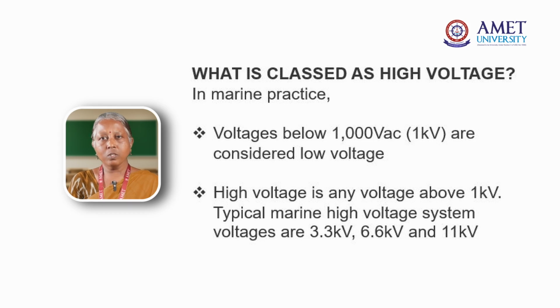So the different types of voltages on board ships are 3.3 kV, 6.6 kV and 11 kV. The number of generators on ships depends upon the requirement and size of the ship. So it may be a medium sized ship or a large ship or a cruise liner. For a large ship, it may need three 6.6 kV generators or one or two 11 kV generators. But for a cruise liner, because it is public transportation, the generator voltage varies according to the size of the ship. So when it goes to high voltage, safety is a very important aspect on board ships.